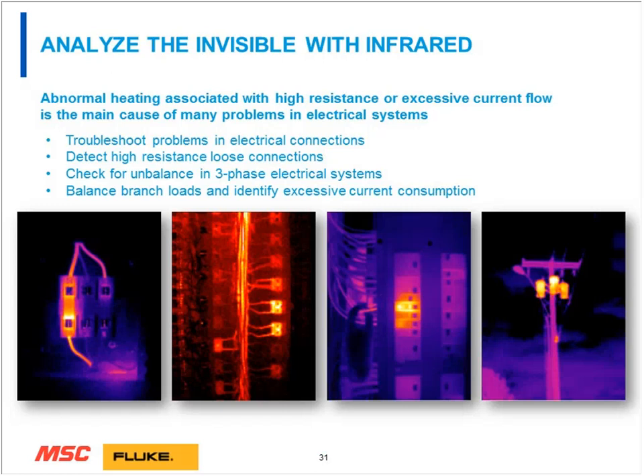Here's some pictures from analyzing the invisible really with infrared. You can see the active conductors starting at the left drawing of some breakers or some fuses. You can see which ones look cool, in which case you may assume that that one might be even an open fuse. You might see some circuits that appear brighter and lighter in color. That can indicate excessive current on that circuit, perhaps even a lighting circuit. Finally, until we get to the right one, which shows some pole-mounted transformers, you can actually look at the oil levels inside a pole-mounted transformer from a distance and indicate some potential problems.